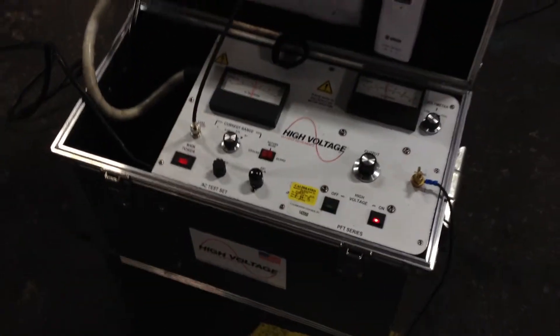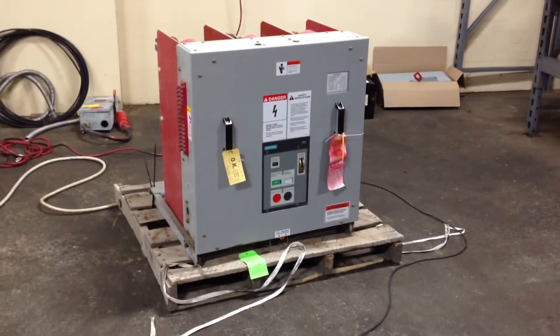So that's what we do. We Megger, Ducter, and hypot all vacuum breakers that come in for stock.